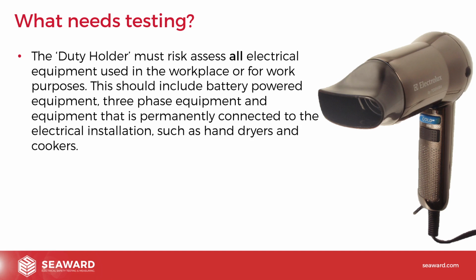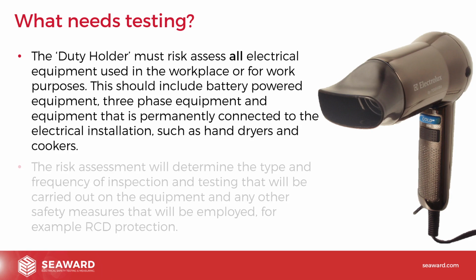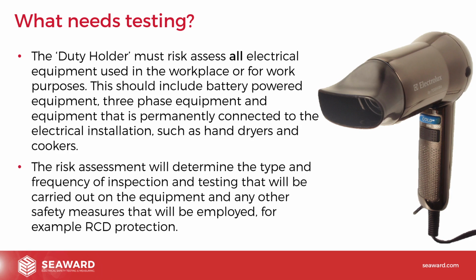So the duty holder must risk assess all electrical equipment used in the place of work or for work purposes. This should include battery-powered equipment, three-phase equipment, and equipment that is permanently connected to the electrical installation, such as hand dryers and cookers. The risk assessment will determine the type and frequency of inspection and testing that will be carried out on the equipment and any other safety measures that will be employed, for example, RCD protection.